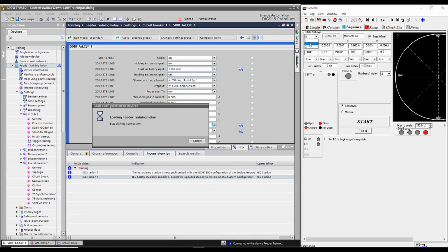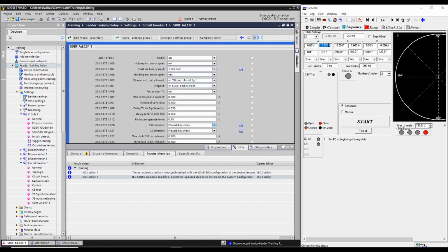I will inject a current in the second stage, here it is, 0.3. Now in the third stage, all I did was reset the current, but didn't reset the breaker state. What will happen here is that it will trip, but won't reset until the breaker state is removed. Let's remove it now. The breaker state reset. Clear. Nice.